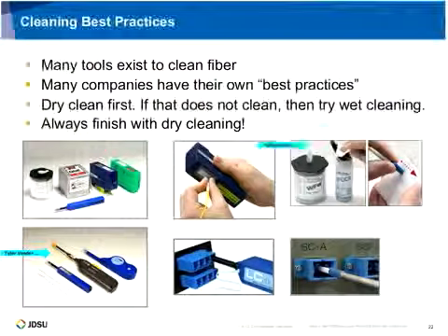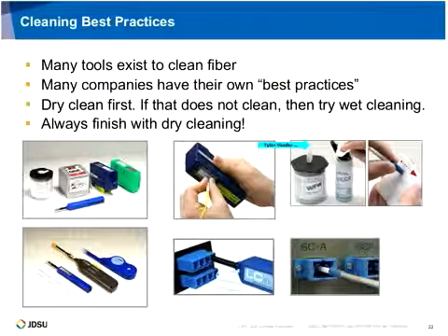Also just highlighting there's some solvents here and such that if you got some stubborn debris, things like that can be helpful. But my recommendation is that if you do use a solvent, follow that up with a dry cleaning process afterwards so that you can help remove some of that solvent as it evaporates.